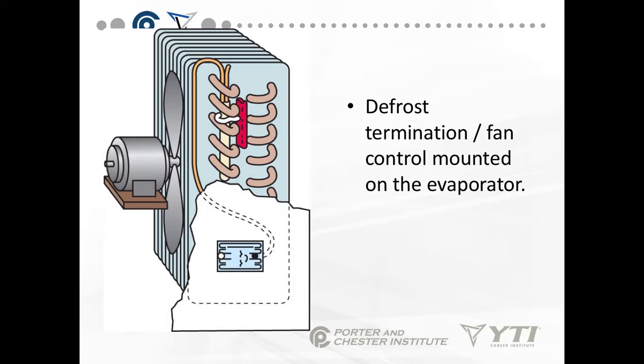To summarize: the defrost termination fan control terminates the defrost cycle once the ice has melted off the coil. It is an energy savings device that protects the compressors and protects the product. The fan delay portion ensures we're not blowing warm, moist air around a frozen environment, which would create snow and frost buildup on the product.